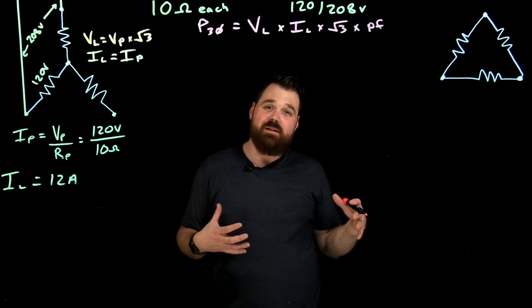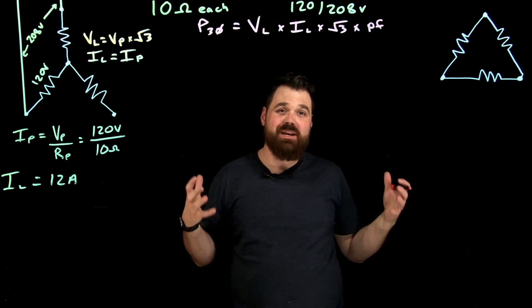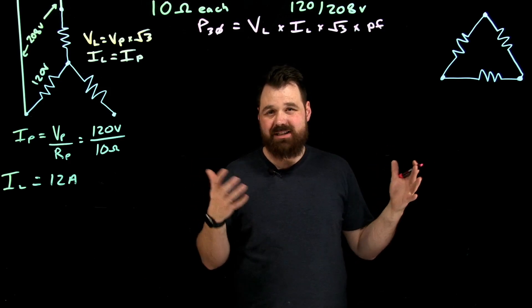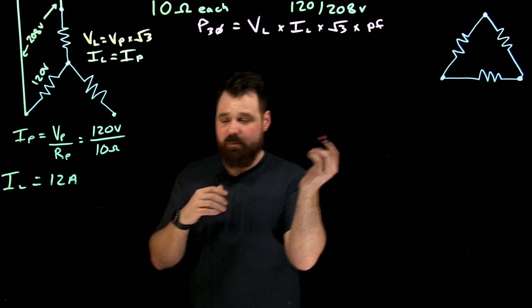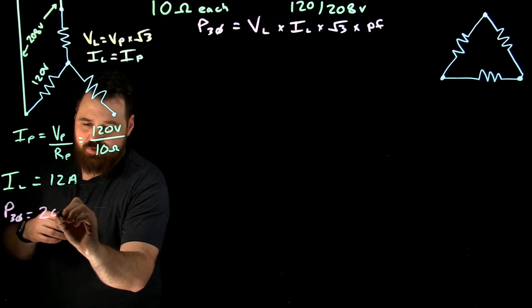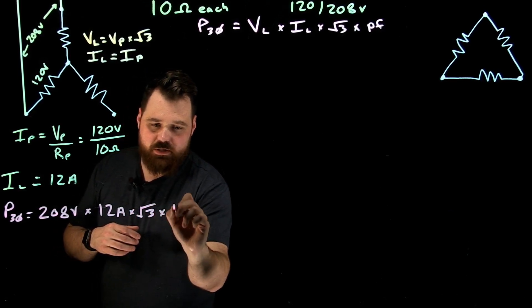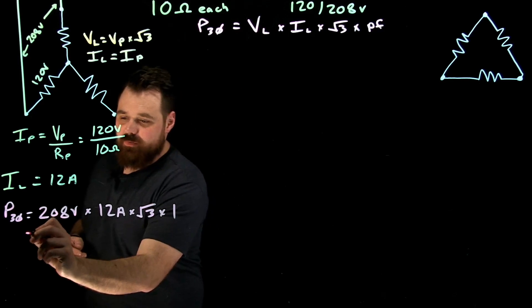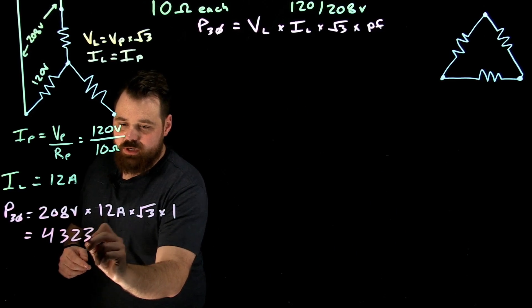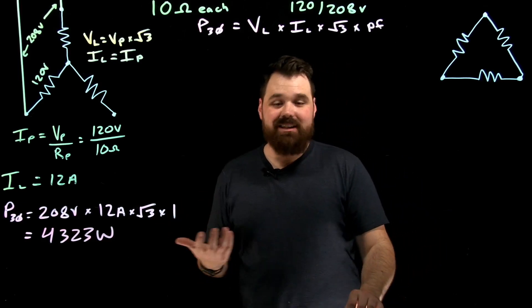Now of course when we're talking about resistors, our power factor equals one. Resistors have a unity power factor or a power factor of one. So my Watts and my volt amps will be the same. My Watts and my VA are the same, but I'm going to take that formula. I'm going to go power three phase equals 208 volts times 12 amps times root three times one, my power factor. And if I were to connect my resistors this way, I would get 4,323 Watts. I'd also get 4,323 VA because my Watts equal my VA.